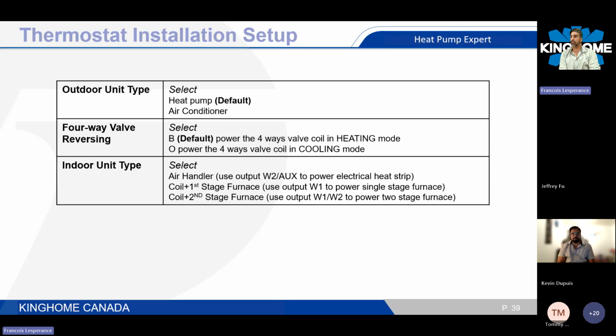Installation setup. So now we're talking about what the guys already did during the installation. So maybe on a service call, you just want to look over, making sure every selection was good. So on the outdoor type, there's heat pump or air conditioner. By default, we're always using heat pump. Four-way valve reversing: every Kinghome unit is powered by the B terminal in heating mode. So this is the default setup that we put inside this thermostat. For example, if you need to power it up like another brand that uses O to power up the reversing valve in cooling mode, then you can do the selection over here.